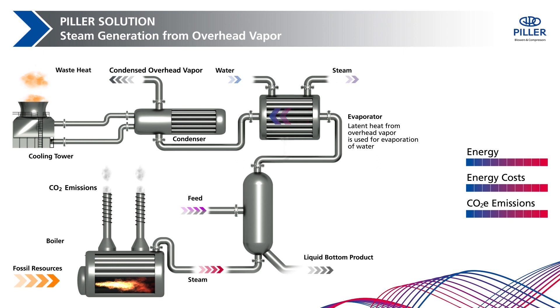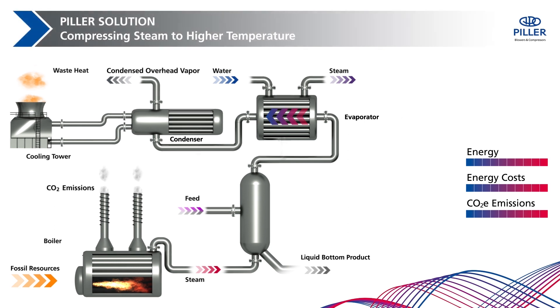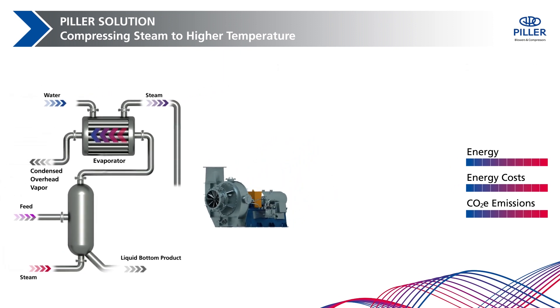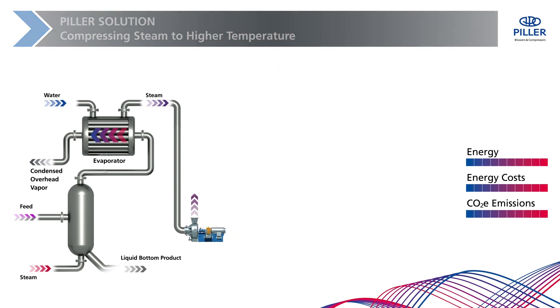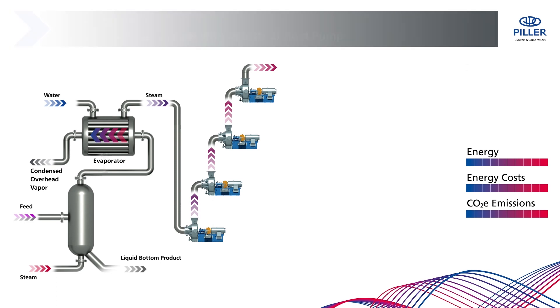The evaporator is specifically designed to meet the required heat demand and process conditions, defining the mass flow and temperature of the generated steam. The system's core is the compression with Piller's perfectly engineered high-performance blowers. For high temperature differences, a multi-stage blower system lifts the waste heat from low temperature back to a usable temperature while preserving the heat of vaporization.